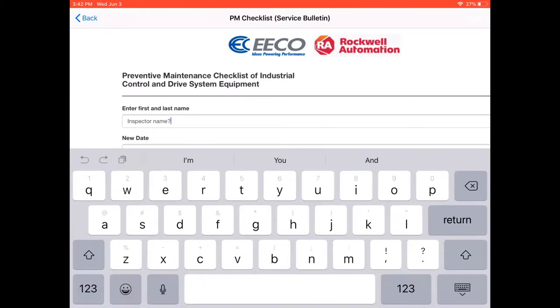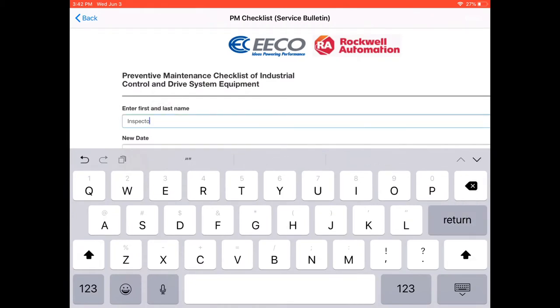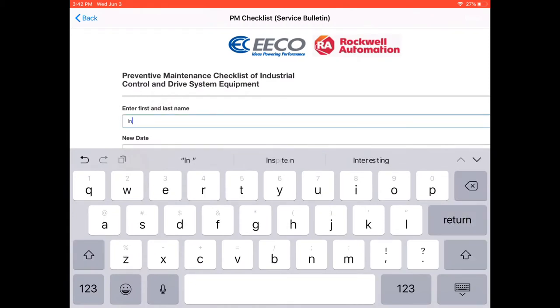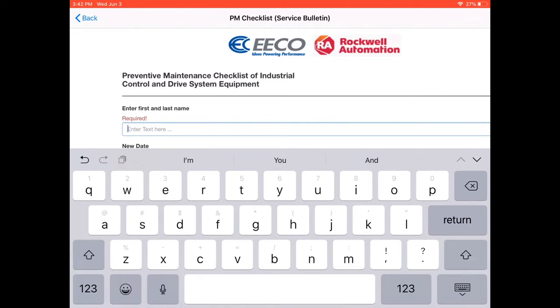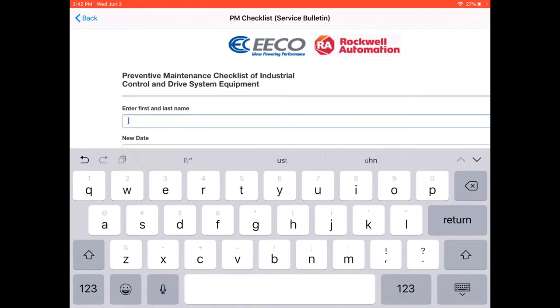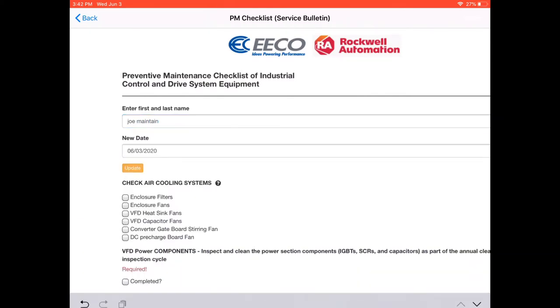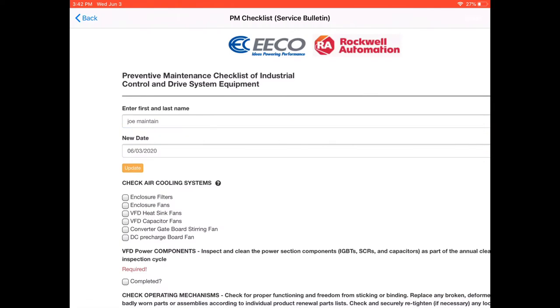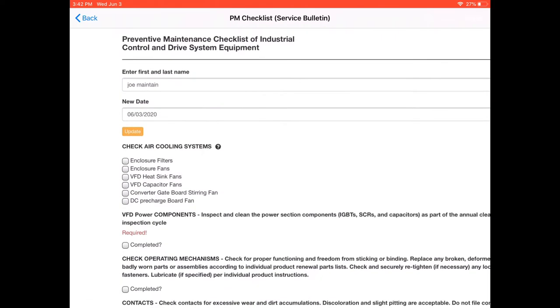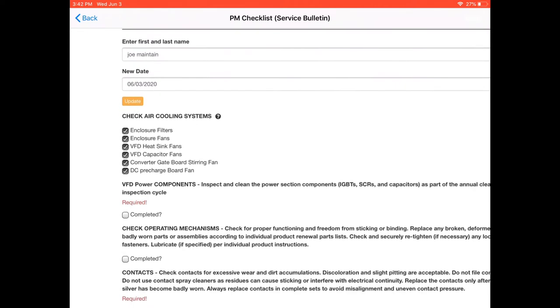First thing it asks for is the inspector's name. Then it automatically puts in the date. The second thing it asks us for is to check the air cooling systems: enclosure filters, enclosure fans, the VFD heat sinks, VFD capacitor fans, converter gate board stirring fan, DC pre-charge fan. After we do these things we check these off.